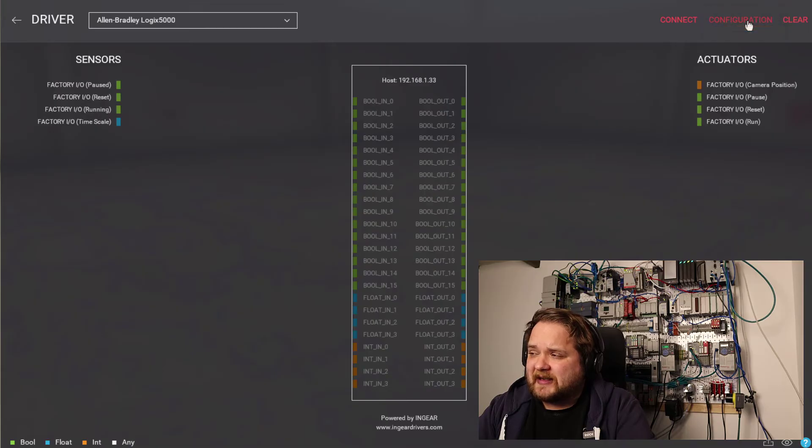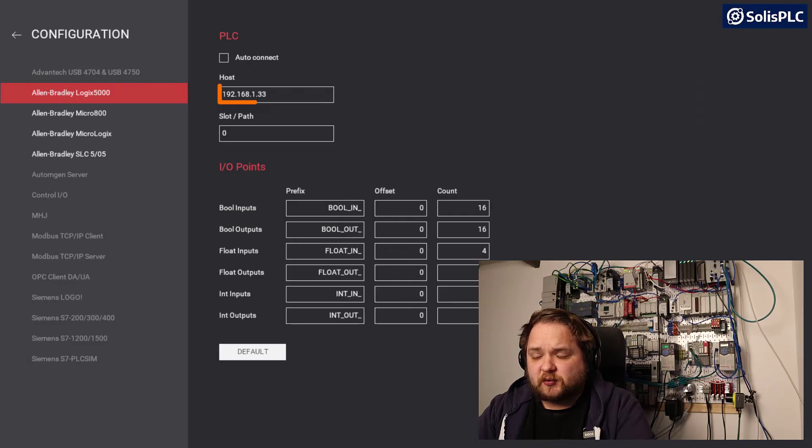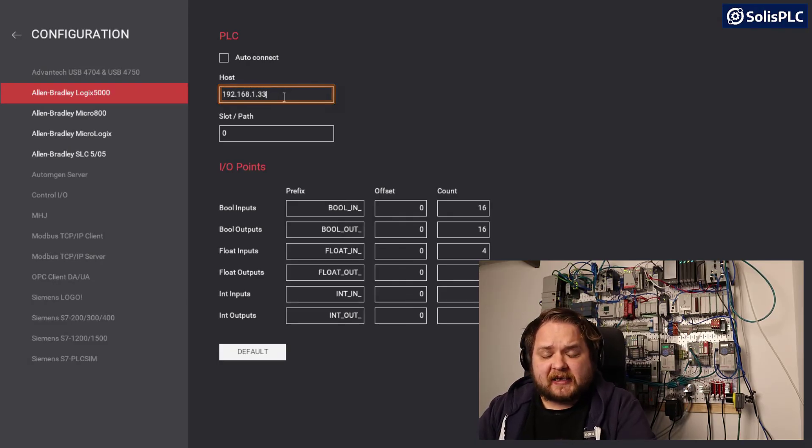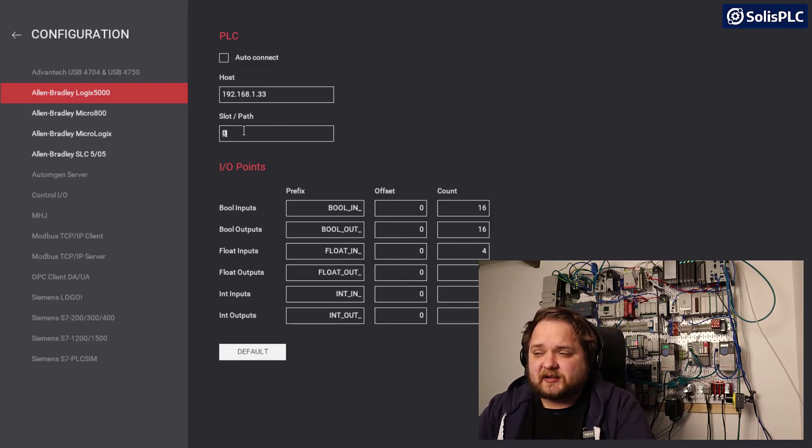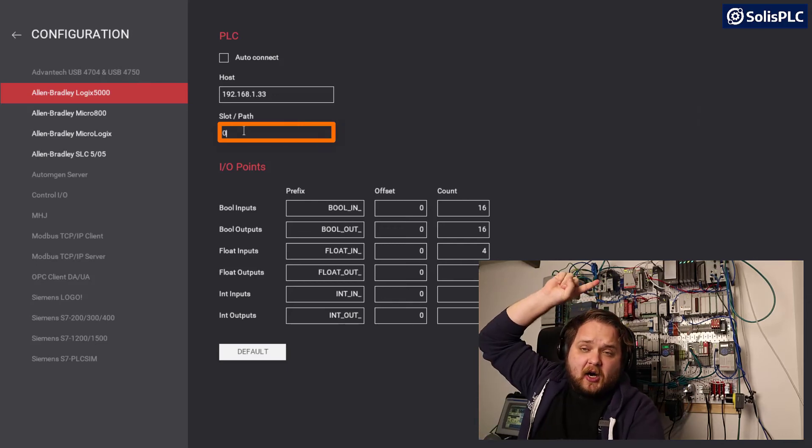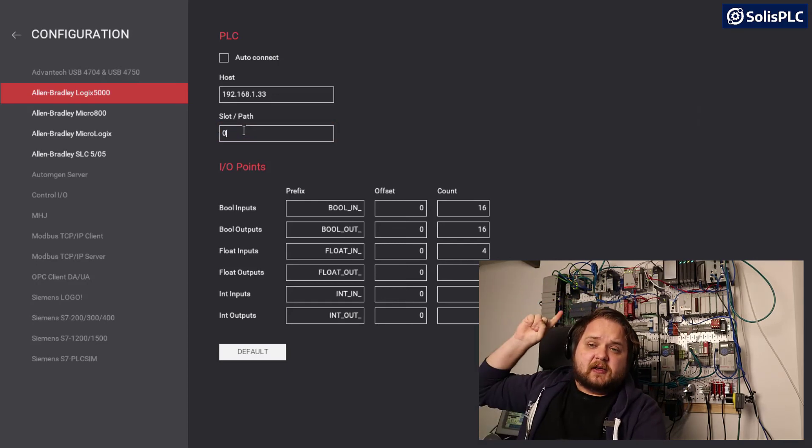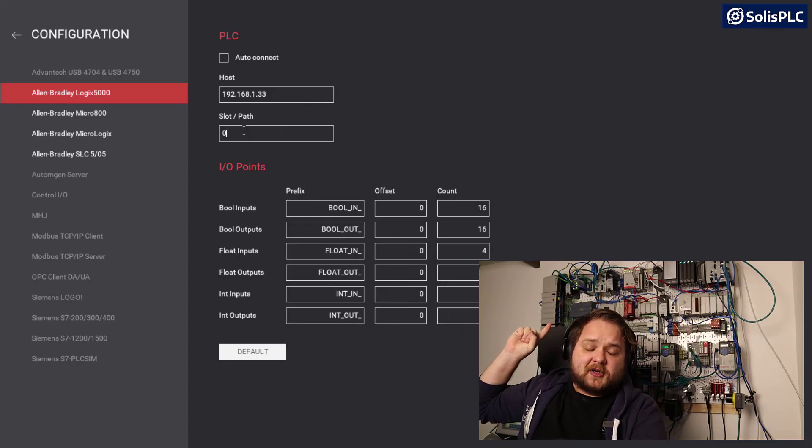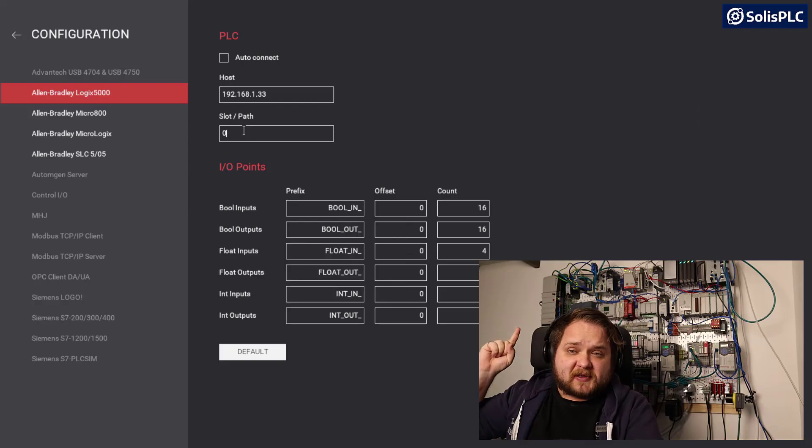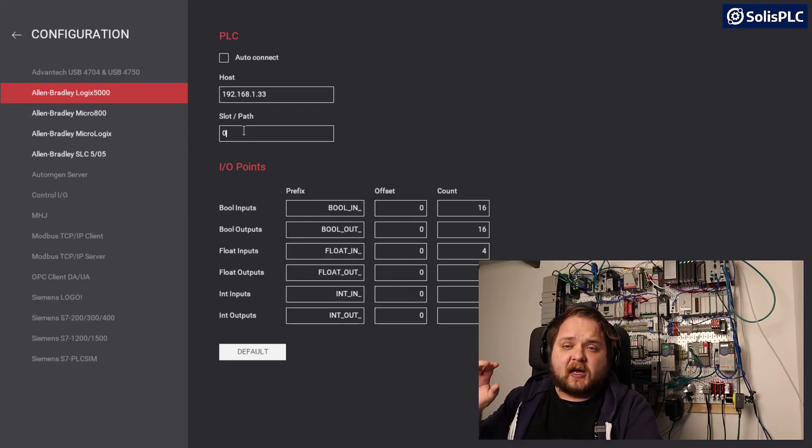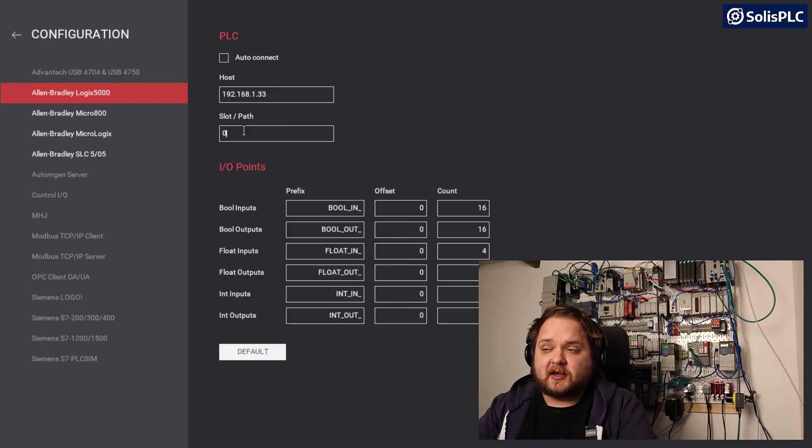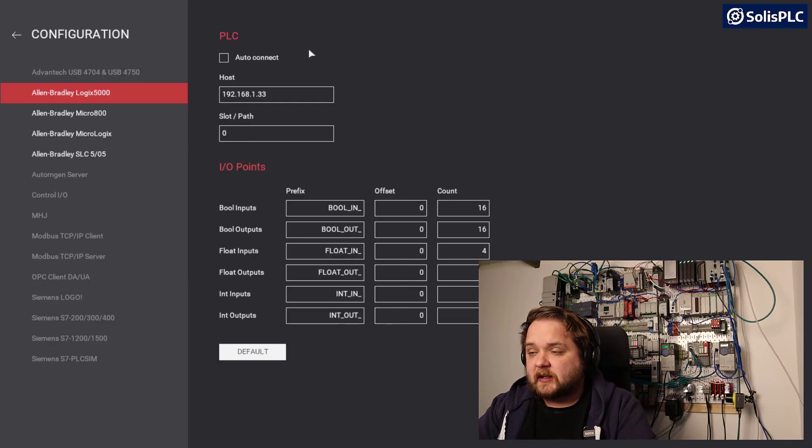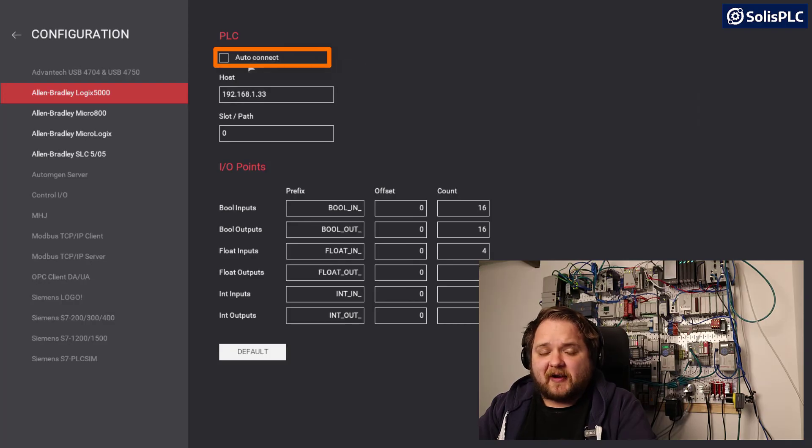We're going to configure this in a later tutorial, however I still want to connect in this video. I'll navigate into configuration and you need to double check the IP address which is 192.168.1.33 in my specific case. The next item is the slot/path. This compact logix is different than the control logix in that I'm going to have to specify a slot for my controller. It's possible it's going to be slot zero, but in the real environment it may not be, so having the right slot/path in this field is going to be important.